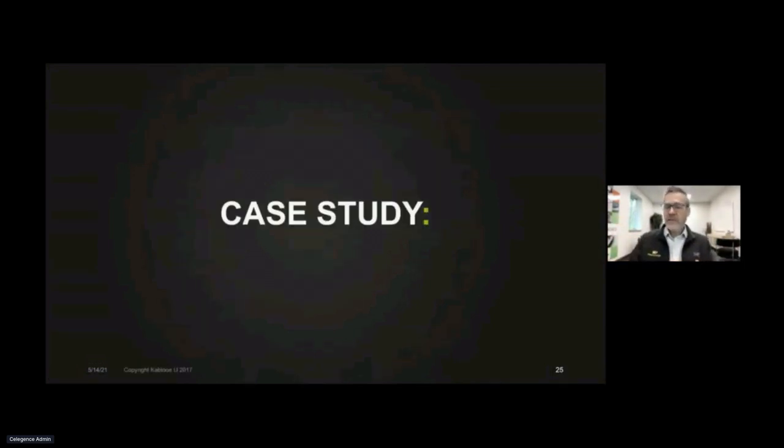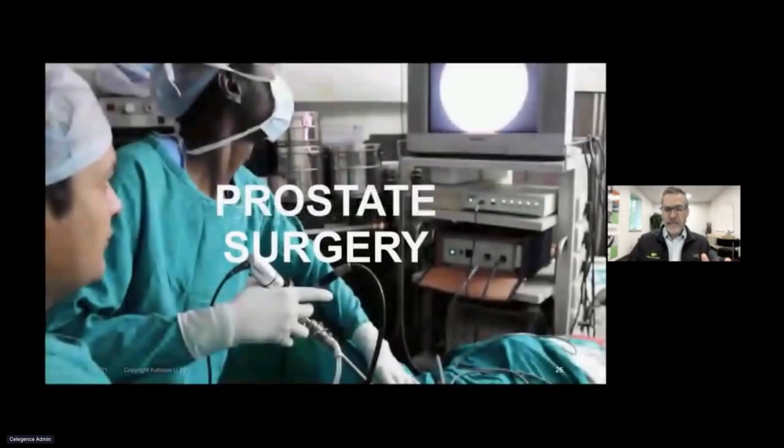And so I want to show a little case study here. In this case study, let's look at a device that was developed for prostate surgery. This is something that we actually did. This is a real case study. So we were taking a look at prostate surgery, and in the beginning of this development process, we're in this early evaluation, in this early research phase. If we think about all of our other design controls, everything that's going on with our quality management system and design controls, we're really in a pre-design control phase right here. We're in phase 0 at this stage of the game. But human factors engineering activities begin in phase 0.